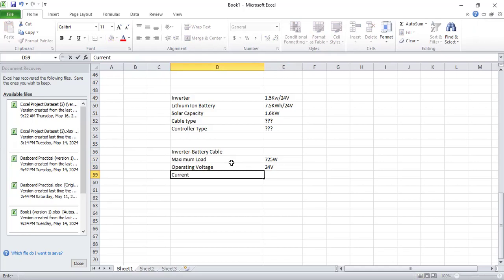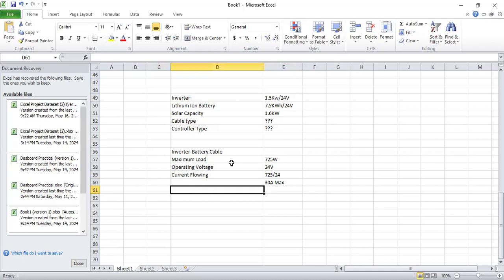that will be flowing through this cable, the current that will be flowing will be simply 725 divided by 24, which gives us 30 amps. So now we know the maximum is 30 amps. That is when all the appliances come on board, when they're all powered. The maximum current that will flow between the inverter and battery cable is 30 amps.